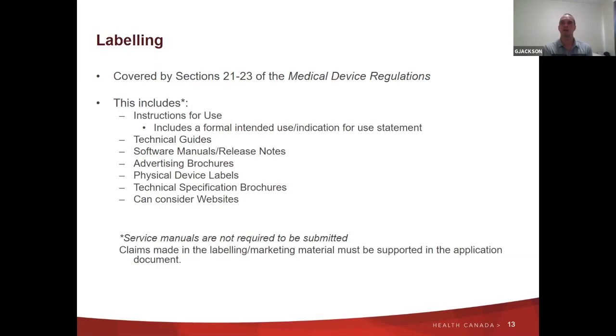We want to see instructions that will allow a user to safely and effectively use the device, depending on how complicated it is, what it's treating, and who's using it. There's a range of what we would require in the labeling, and that's something we can ask for revisions on, or changes, or specific requirements, saying this is only available for this use in Canada. These kinds of things do come up at times.